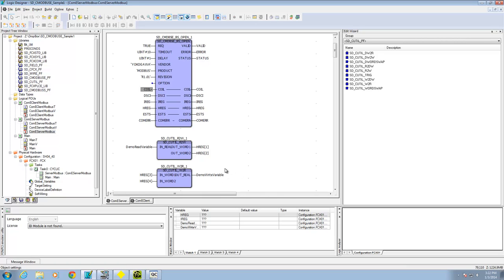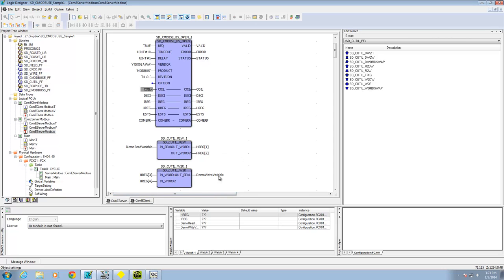For set points or variables that might exist in two places — like the HMI, where the HMI could set it, or maybe some internal Stardom code like set point tracking — you'll need to write your own code to determine when to use the value from the HMI versus the one from internal logic. This video is really just showing you how to get basic communications up and going. Here are the three basic blocks you'd use to read a variable into an HMI and write from an HMI into a variable inside the Stardom.